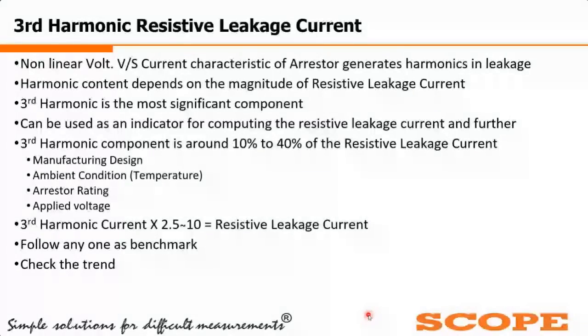And this 10 to 40%, how has this figure come? Because it varies with various other parameters like the manufacturing design and the ambient condition. In the sunny day, the wet dry condition, the leakage current value is X, and immediately there is one splash of rain, or the temperature suddenly goes down, and if we measure immediately after that, we will be getting a totally different value than X. So it is closely associated with the ambient condition, temperature, moisture, earthing condition, everything. Then comes the arrestor rating, whatever is the rated voltage of the arrestor, and at the time of measurement how much actual voltage is applied. Now this applied voltage is nothing but, at the time of measurement, whatever voltage is available in the system.